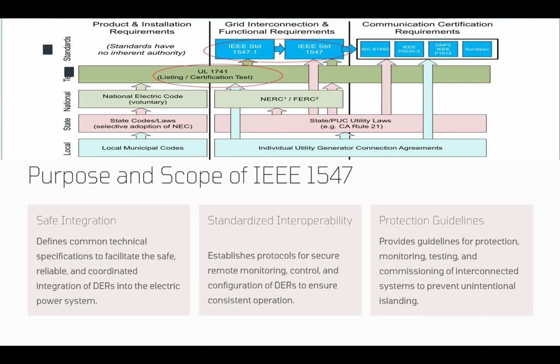If they don't do that and they switch to islanding mode, it would violate the de-energization of the part of the grid that is under maintenance, and you can see how dangerous it would be for the workers that are maintaining and working on those equipment and our system. Now, to meet the safe integration, this standard also establishes the trip and reconnection rules, so we prevent some unsafe energization of the grid.